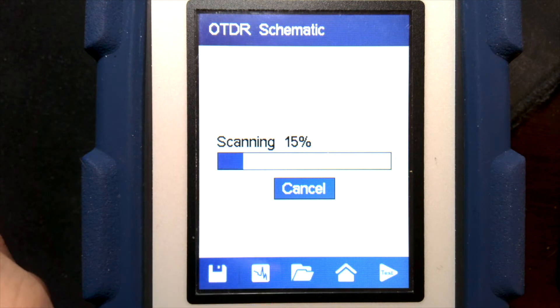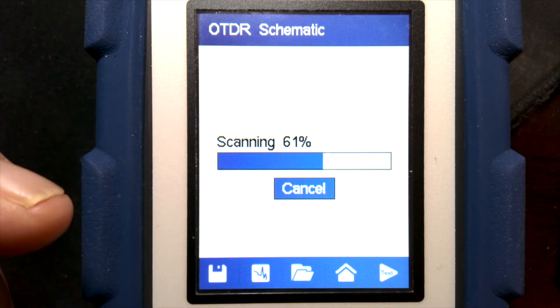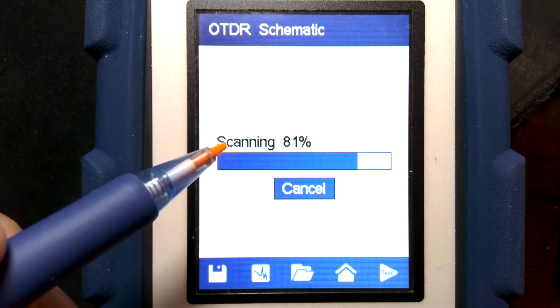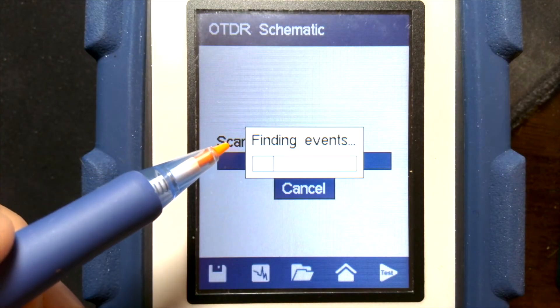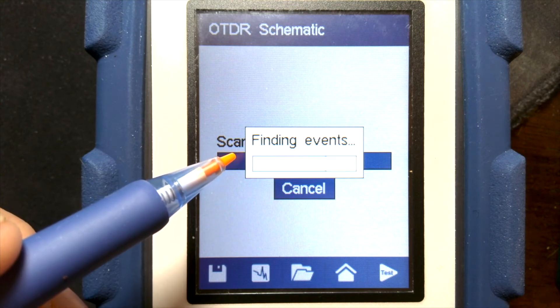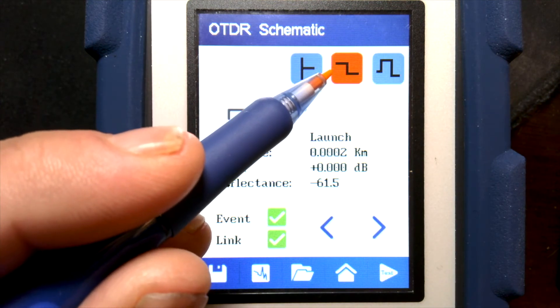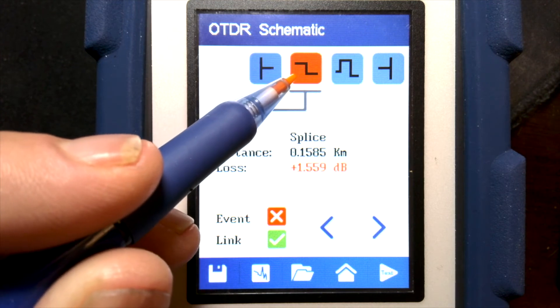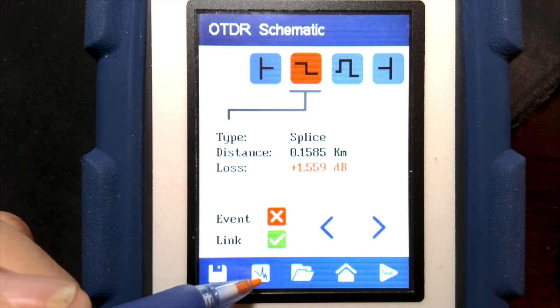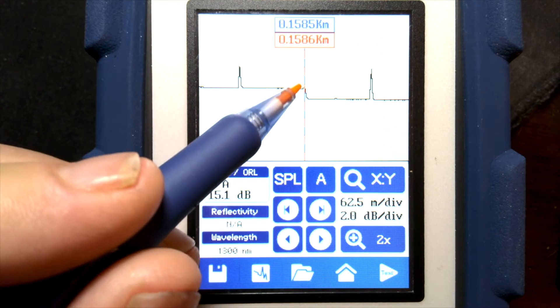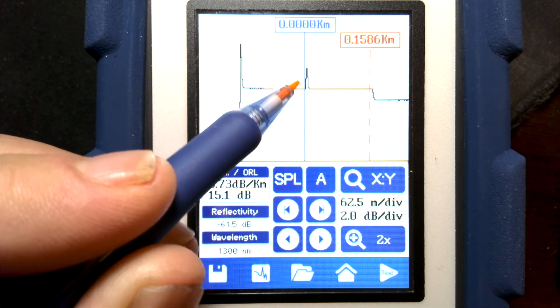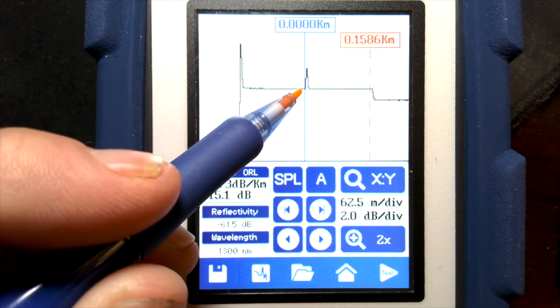We won't change anything else — we'll just run the test again. All we've done is tick that box to turn the launch cable setting on. Now the first event will actually be that splice that was the second event before. Once it's finding the events, we'll get our schematic view, and we'll see the first event is this launch. Our first real event is the splice, now at 160 meters. The cursor is jumping to this splice. If we scroll the cursor back, we can see that connector that was at 160 meters before is now showing at zero meters.